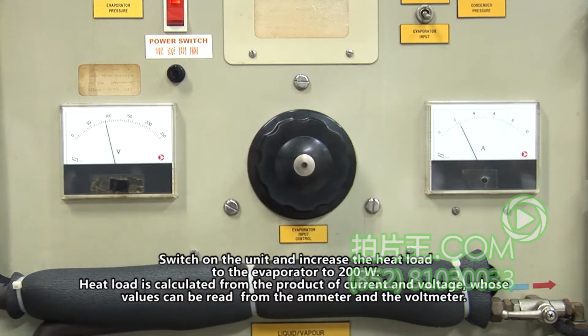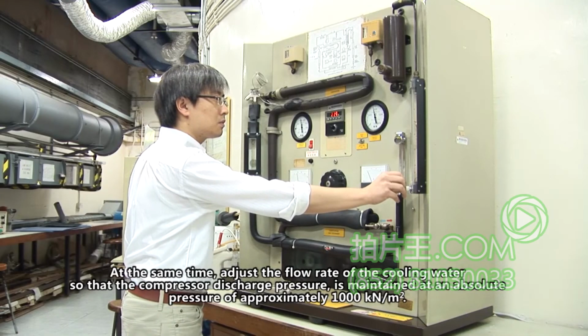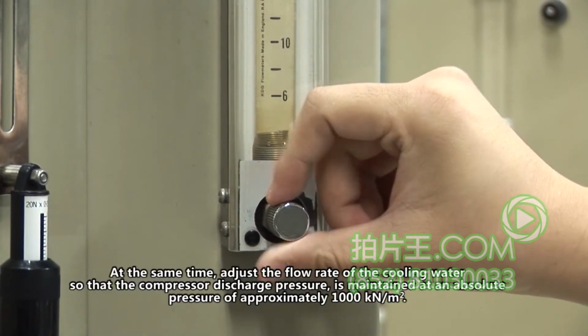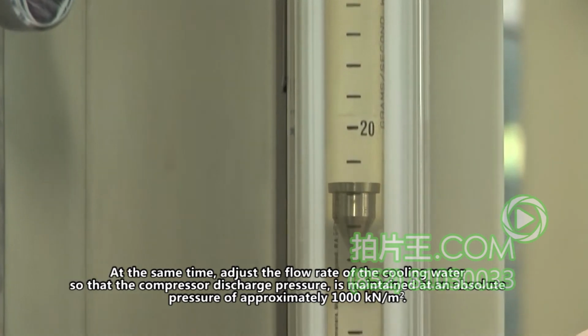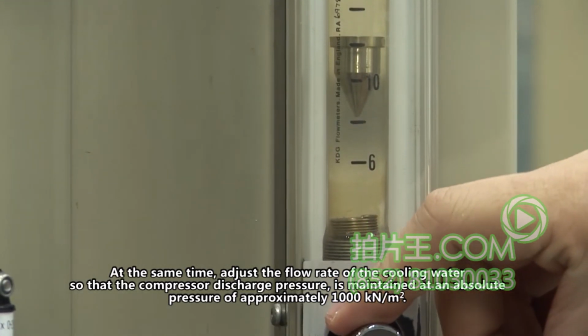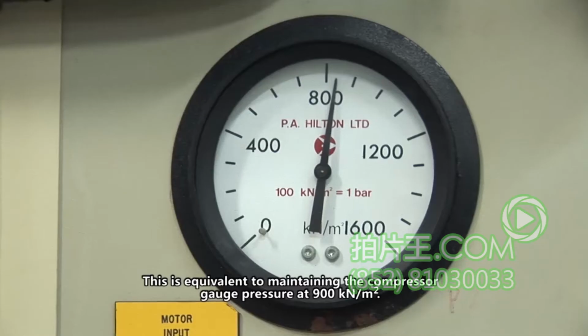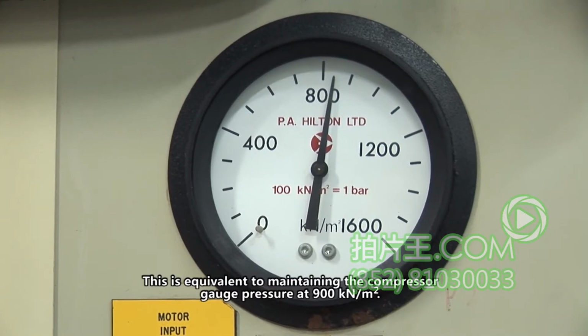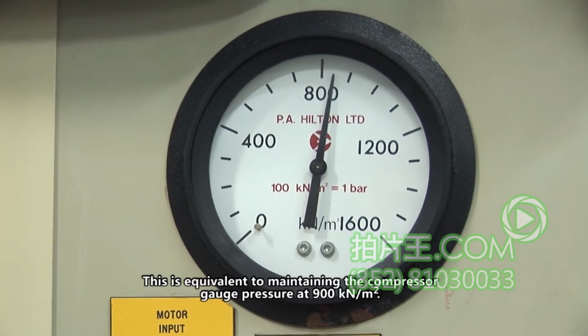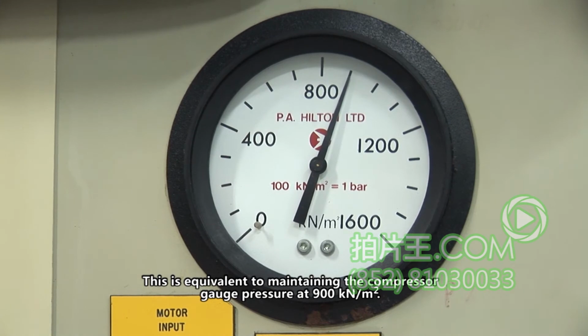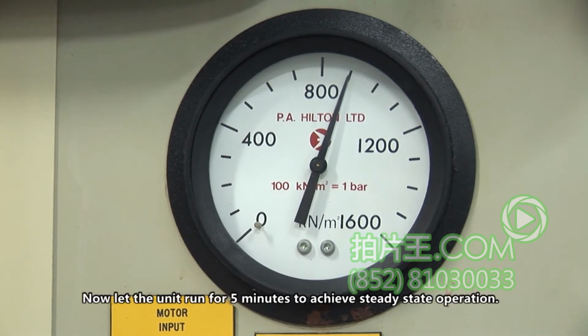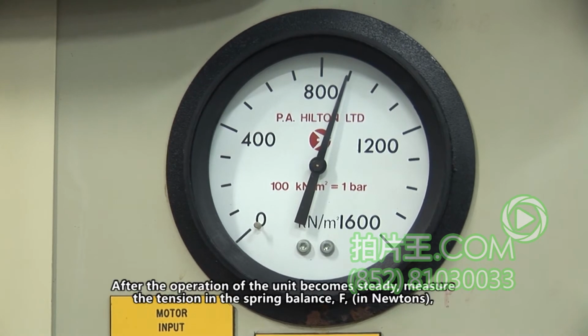the voltmeter. At the same time, adjust the flow rate of the cooling water so that the compressor discharge pressure is maintained at an absolute pressure of approximately 1000 kilonewtons per square meter. This is equivalent to maintaining the compressor gauge pressure at 900 kilonewtons per square meter. Now let the unit run for 5 minutes to achieve steady state operation.